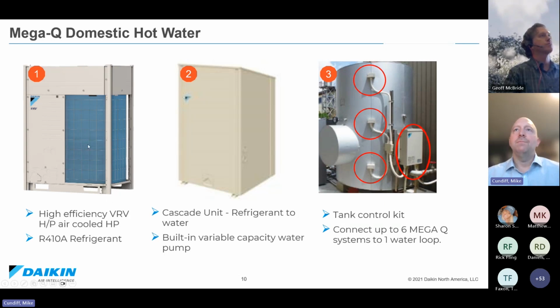So this is a heat pump, 10 tons. It's going to be launched with R410A originally, and then transition to R32. You have a cascade unit here with another booster compressor that gets the hot water to 180 degrees or so. It's got a built-in variable capacity water pump, and then the tank control kit that you need right here. You just need the one tank. You don't need 2 tanks, 3 tanks, whatever. We can do everything with one.